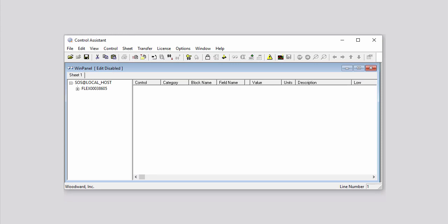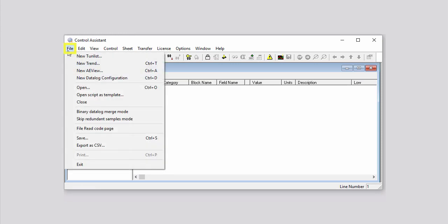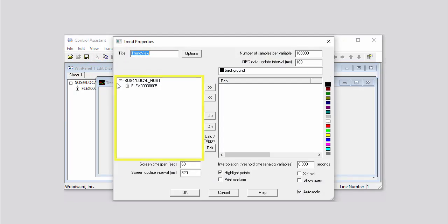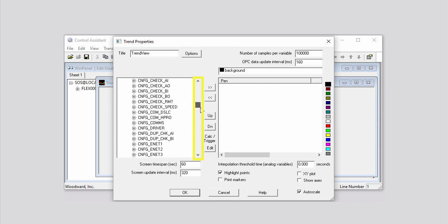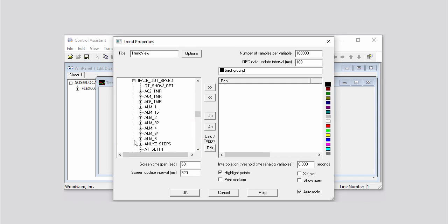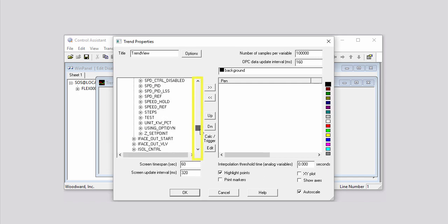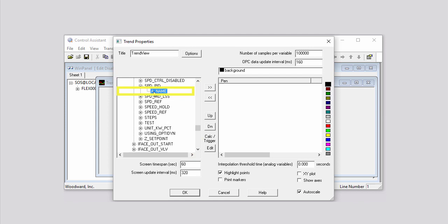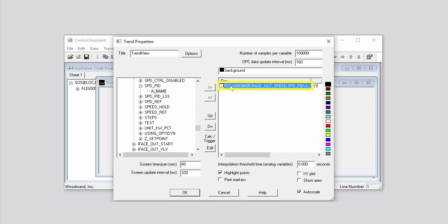You can use Control Assistant to view live trend variables in the controller. To do this, click File on the menu bar, then click New Trend on the drop-down menu. In the list on the left side of the Trend Properties dialog box that opens, click the plus sign next to the name of your controller, then click the plus sign next to the desired category. For this demonstration, we'll select the I-Face Outspeed category. Next, click the plus sign next to the desired block — for this demonstration, we'll select the Speed PID block. Then click the field name or variable you would like to add to the trend. For this demonstration, we'll select the A name variable. Click the right arrow button to add the highlighted variable to the pen list. A pen is another name for a variable to be shown in the graph. Click the variable in the pen list, then select the color you want to associate with this pen by clicking the desired color box — for this demonstration, we'll select Bright Green.